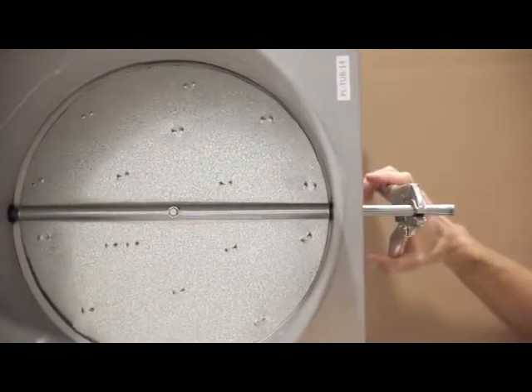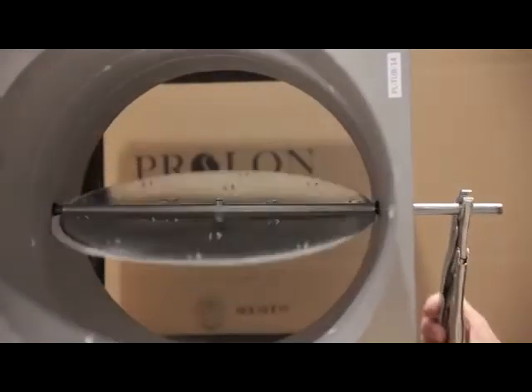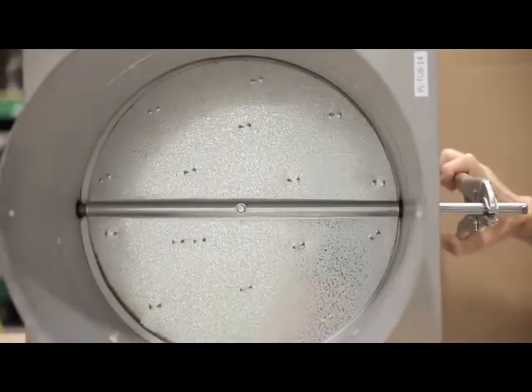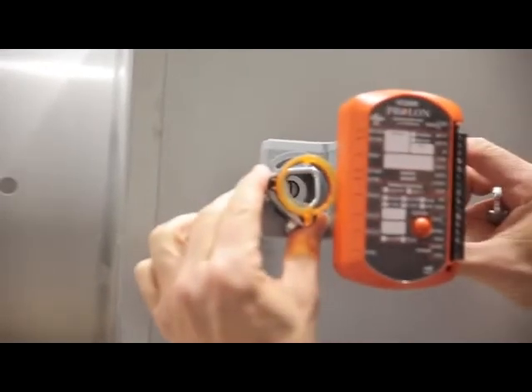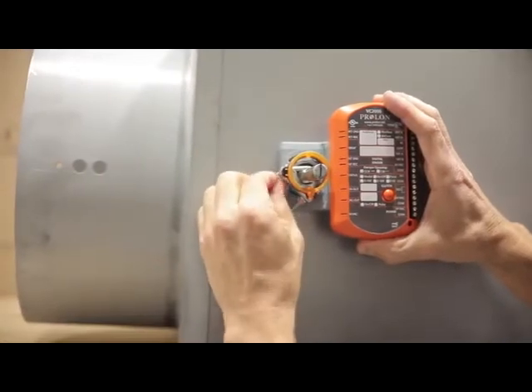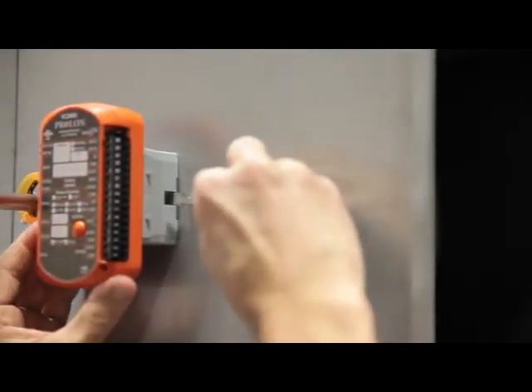Make sure the damper is fully closed before proceeding. Next, ensure that the VC2000's mounting clamp is also in the closed position and matches the opening direction of the damper. Slip the clamp over the damper shaft, tighten the mounting nuts and install the anti-rotation bracket with self-tapping screws.